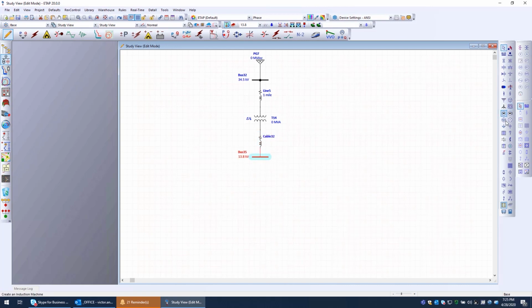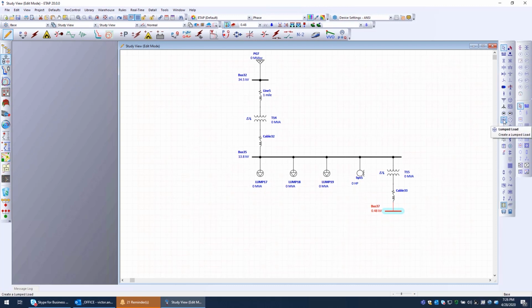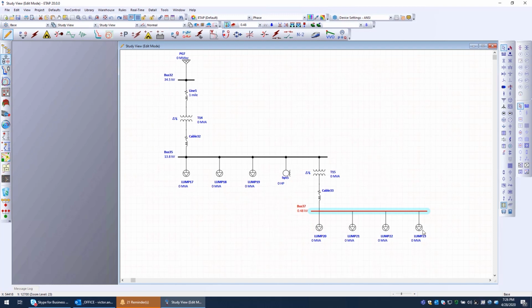This then feeds several medium voltage buildings, feeding also a large pump, which is represented as a synchronous motor, and then stepping down the voltage from 13.8 kV to 480 volts. It's another transformer feeding an MCC. This motor control center will have 4 480 volt motors, and we can actually also use AutoBuild to provide or enter the protective device using the rulebook.